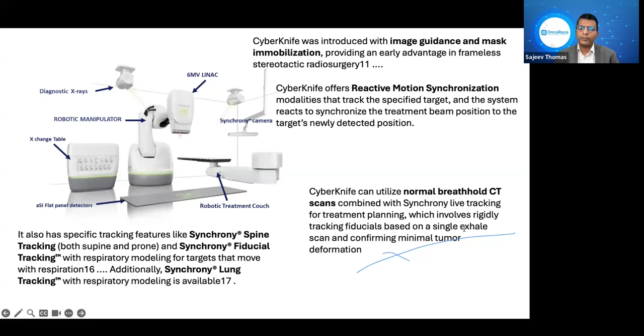This is how the room of the CyberKnife looks. It uses a sophisticated kV X-ray image source, consisting of two ceiling-mounted X-ray sources with corresponding in-floor detectors, and these generate beams that intersect orthogonally, allowing the precise pinpointing and tracking of targets throughout the treatment. The treatment is based on the patient positioning table accurately bringing the patient to the imaging field of view, and that point is known as the image center.